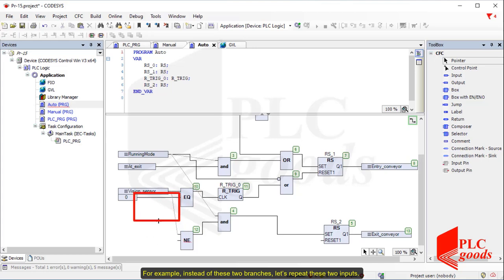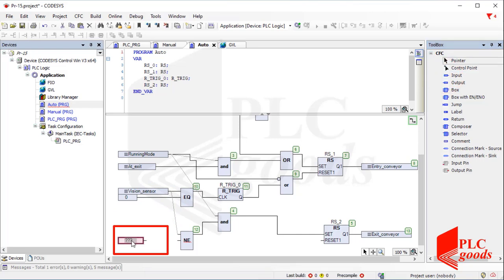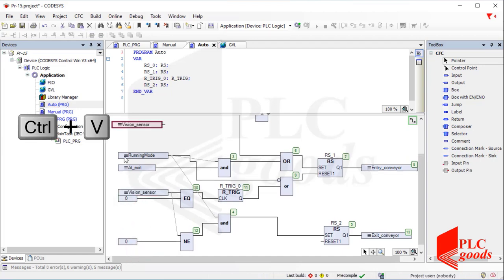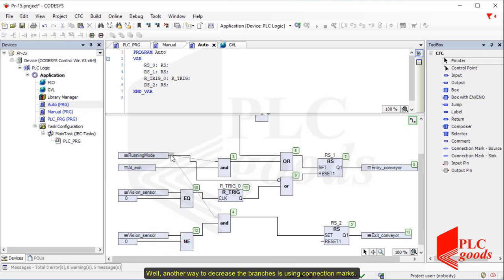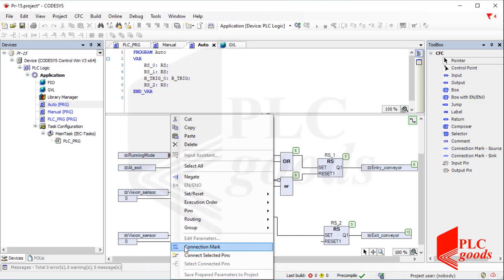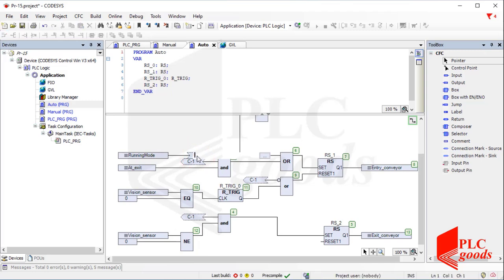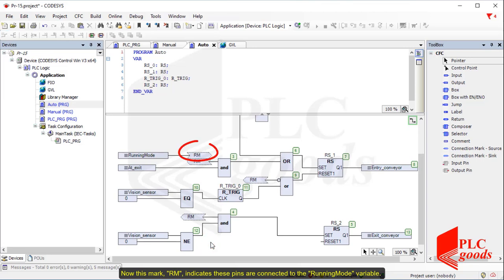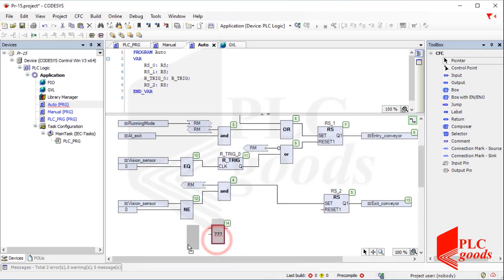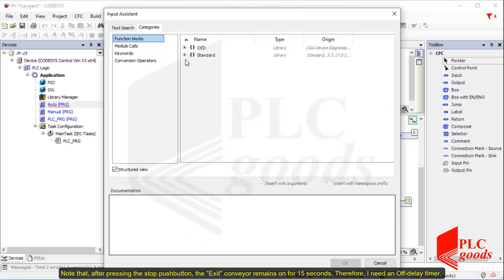If the vision sensor is not equal to zero, it means a new product is below the vision sensor and it needs to be moved by the exit conveyor. Note that inputs can be repeated in the CFC language if there aren't lots of branches that make the program look complex. Another way to decrease branches is using connection marks. I can right-click on each line and use the 'connection mark' option. Now this mark RM indicates these pins are connected to the running mode variable.